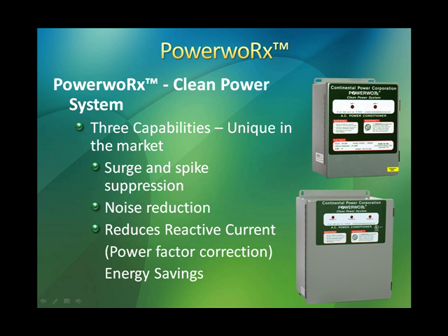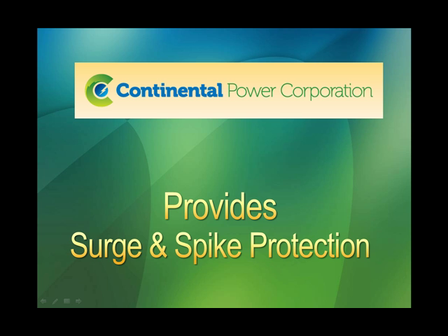PowerWorx, the clean power system, has 3 unique capabilities, unique in the marketplace. These 3 capabilities are not unique in themselves. Each one has been around for decades, actually more than half a century. But what is unique is the way that we apply them, the way that we integrate them together. Those 3 capabilities are surge and spike protection, also known as transient voltage surge suppression, or TVSS. Noise reduction, including harmonic reduction, and then a reduction for reactive current, or power factor correction. And this is the component that, along with noise reduction, can lead to energy savings. First of all, we provide surge and spike protection.